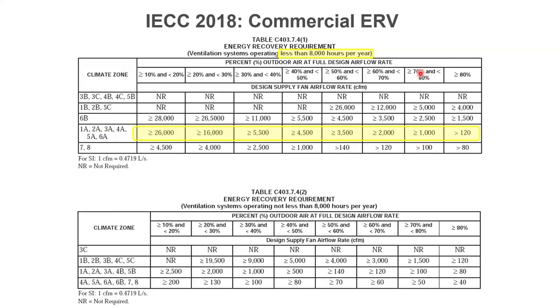So instead of 70%, 5,000 CFM on the supply, if my supply is 1,000 with 70% outside air, I need an ERV. And then it tiers down from there all the way down to 10% outside air on a fairly large 26,000 CFM system. So either a lot of supply air, hence a lot of outside air, or not a lot of supply air but a high fraction of outside air. There's probably better ways they could have made this table, but this is how they decided to do it.